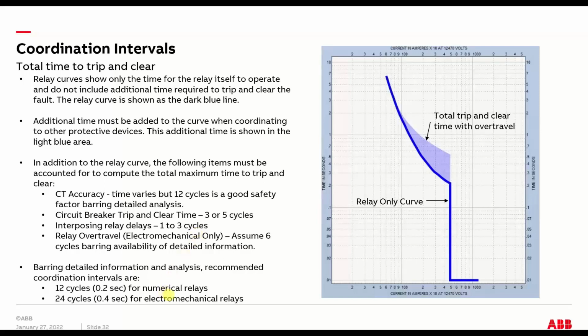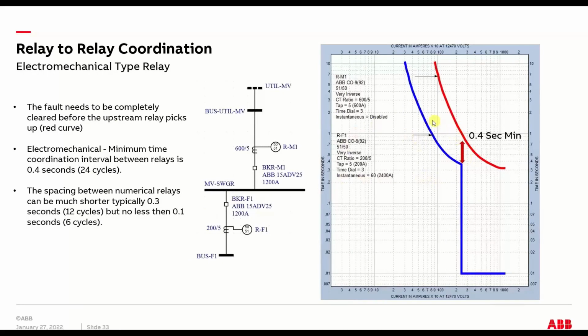But you can get tighter coordination as long as you put the work in of doing the engineering analysis, because there's a lot to it. So that's one of the big things that is different between doing relay coordination versus low voltage breaker coordination. Just kind of further example. Here's a downstream relay and an upstream relay, and I'm just kind of showing electromechanical. And I'm just showing you that's that minimum value you got to set where your upstream relay is away from your lower relay, and that's all due to the speed of the breaker and the accuracy of CTs and a whole myriad of design issues.